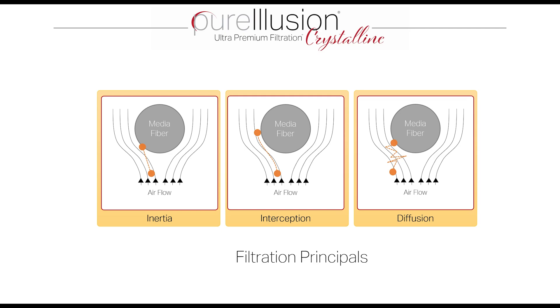When we look at particles even smaller than this, we're talking about the diffusion principle. When a particle is very small — 0.1 microns, 0.01 microns, 0.003 microns — they begin to act in a very counterintuitive way. They become erratic, jutting here and there, bouncing off molecules in the air. The smaller the particle gets, the greater its freedom of motion. And with greater freedom of motion, the more likely it is to encounter a media fiber in the HEPA filter. Thus, for the diffusion principle, as particles get smaller, the efficiency of filtration gets larger.